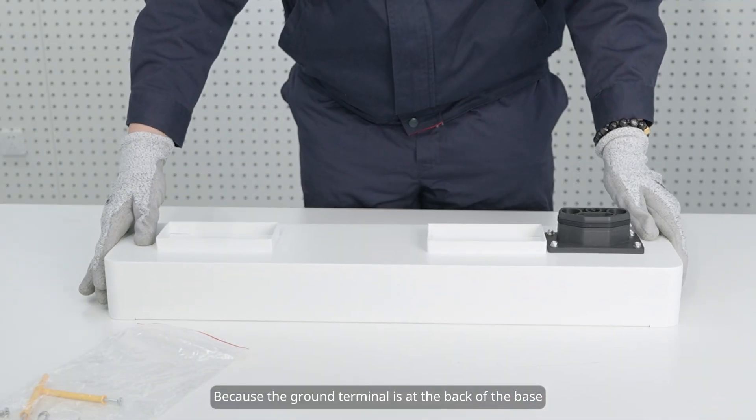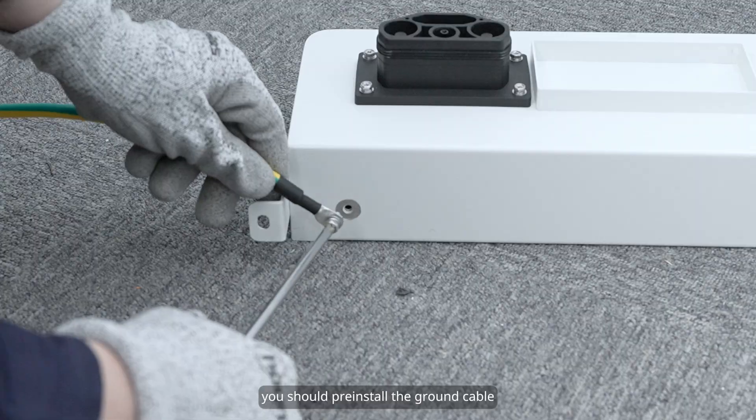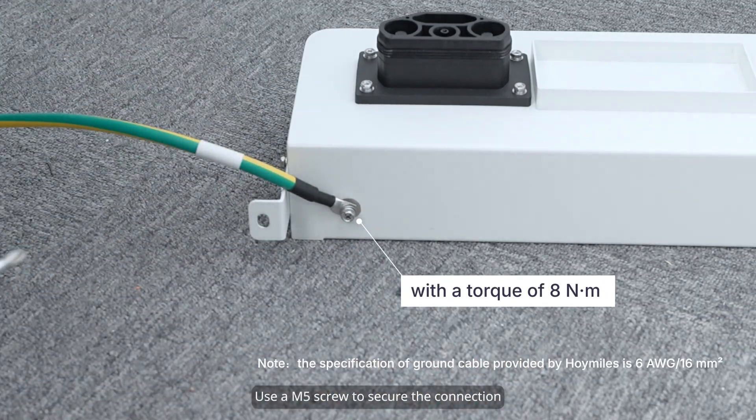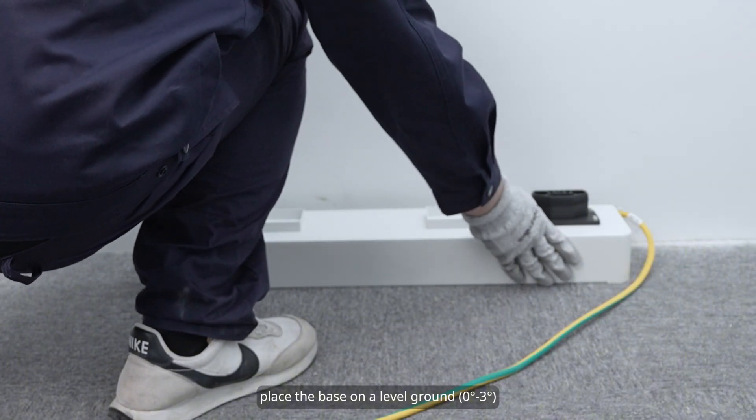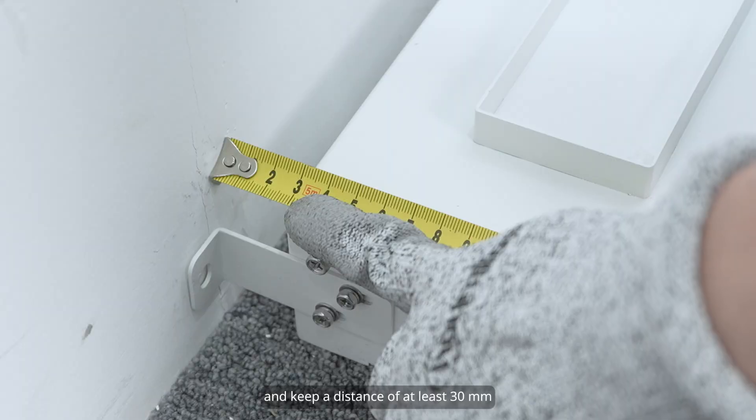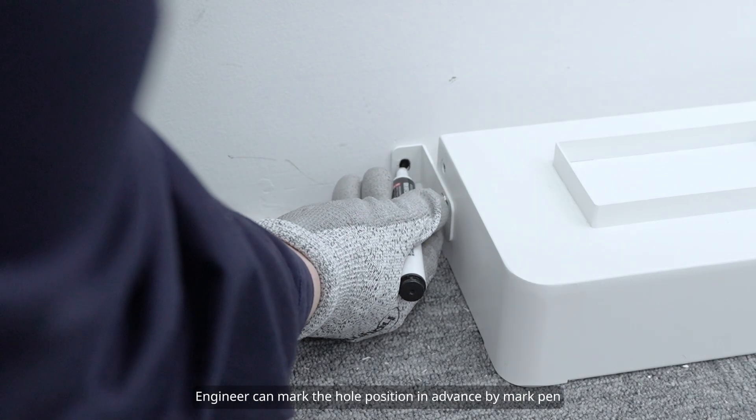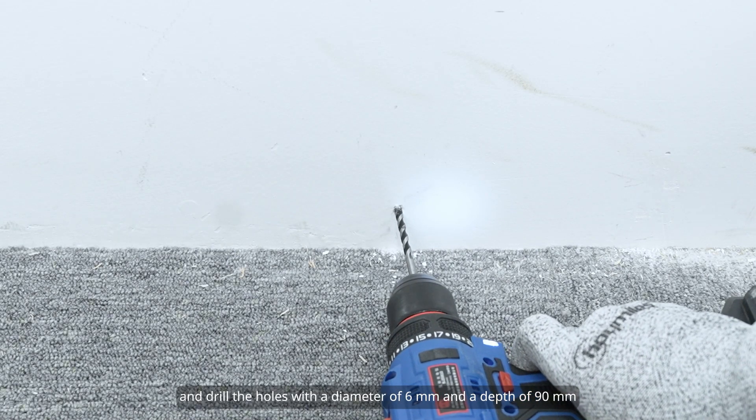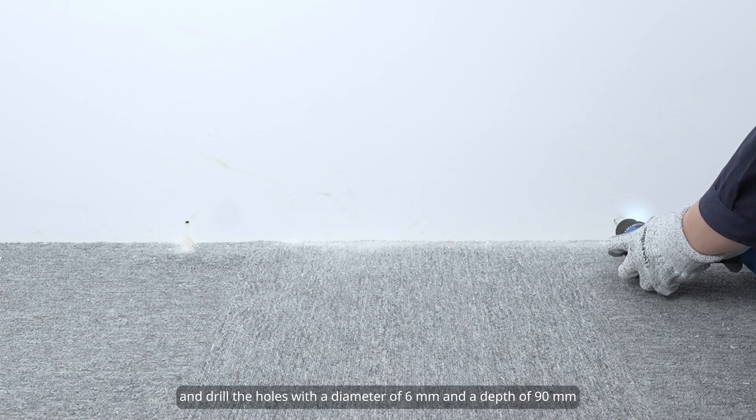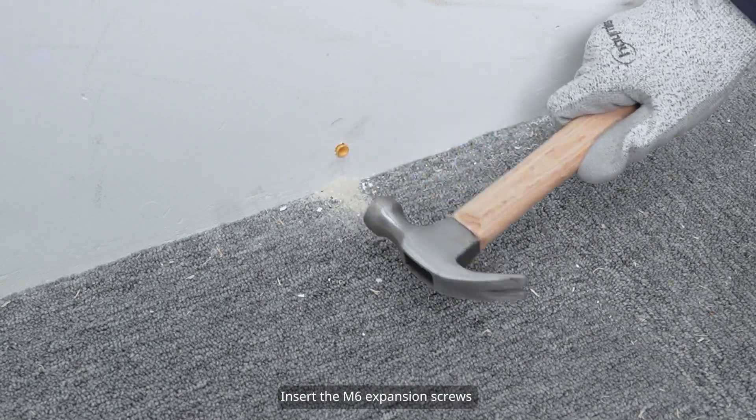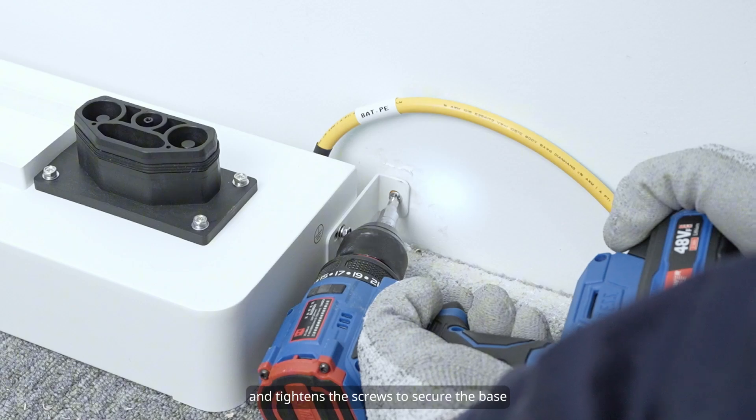Because the ground terminal is at the back of the base, you should pre-install the ground cable. Use M5 screw to secure the connection. Place the base on a level ground, parallel to the wall, and keep a distance of at least 30 millimeters. Engineer can mark the hole position in advance by mark pen, and drill the holes with a diameter of 6 millimeters and a depth of 90 millimeters. Insert the M6 expansion screws and tighten the screws to secure the base.